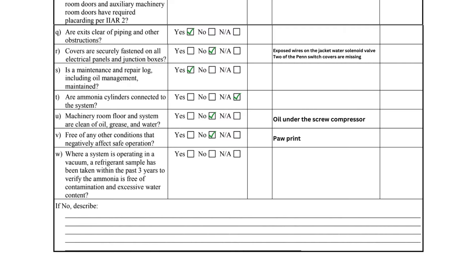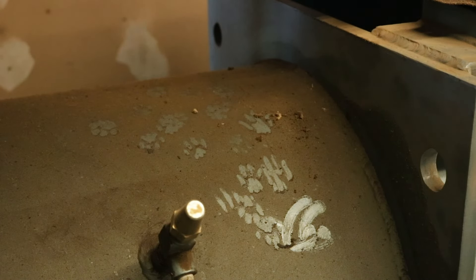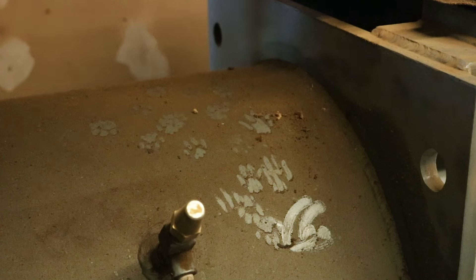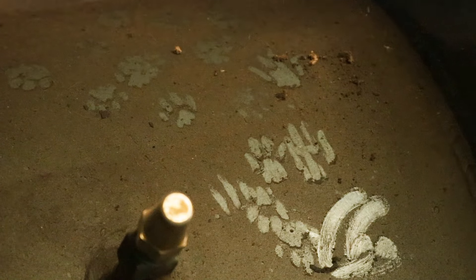Item V serves as a catch-all for other concerns that the inspector may have observed. The area at the bottom of the checklist can be used to write a description of the deficiencies. For example, paw prints were observed on an oil separator, which is an indication that an animal has been inside the machinery room and must be corrected.